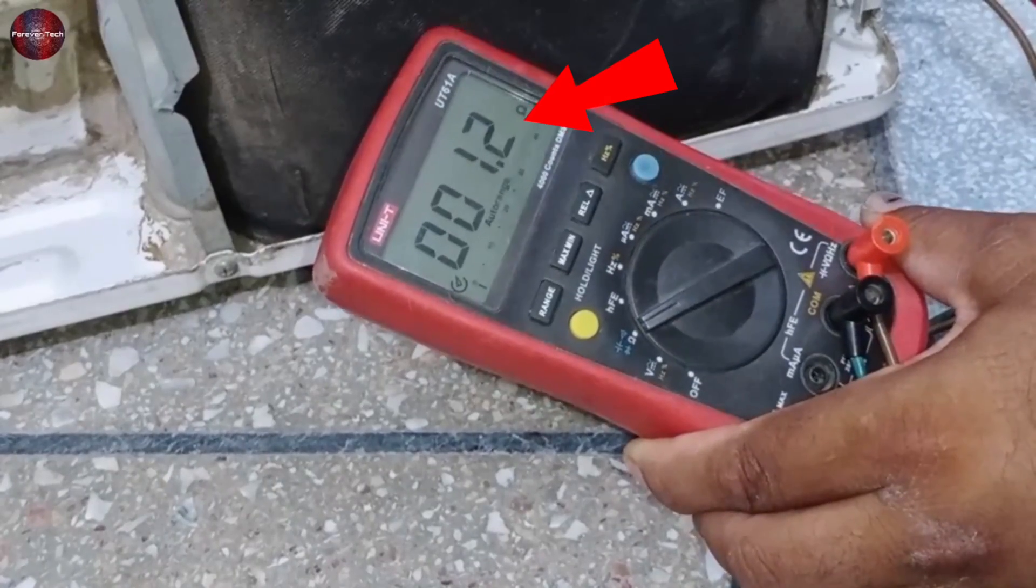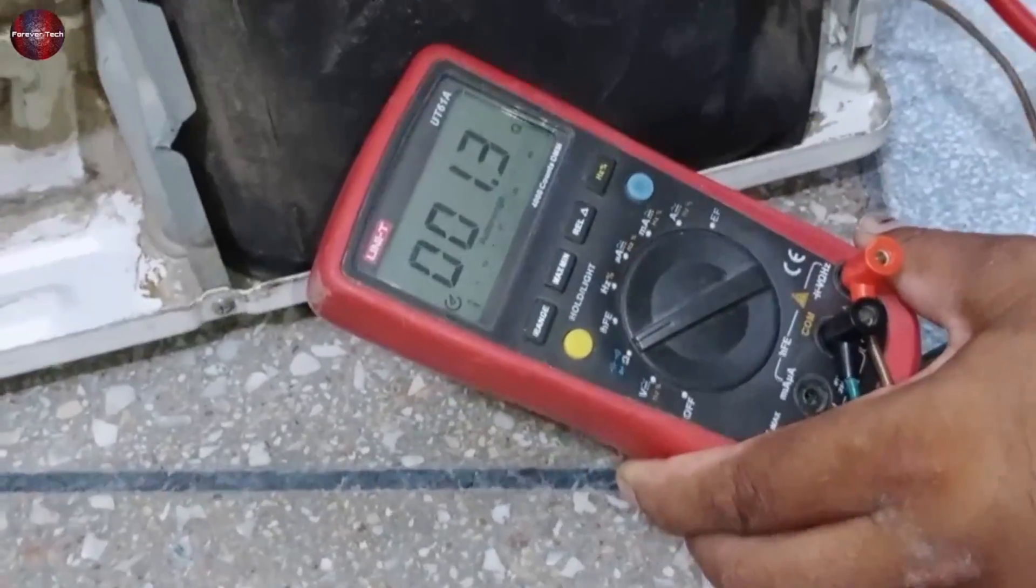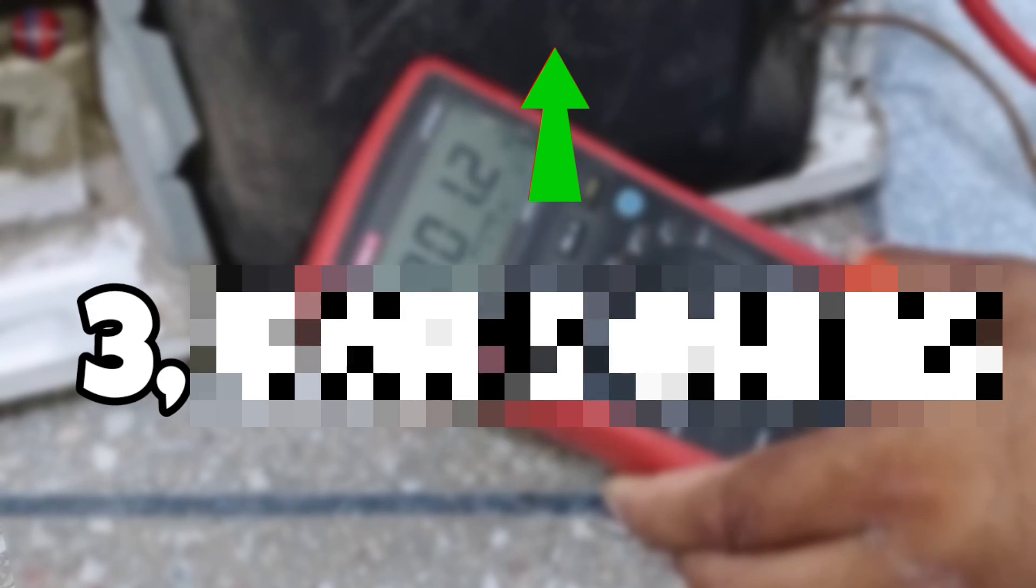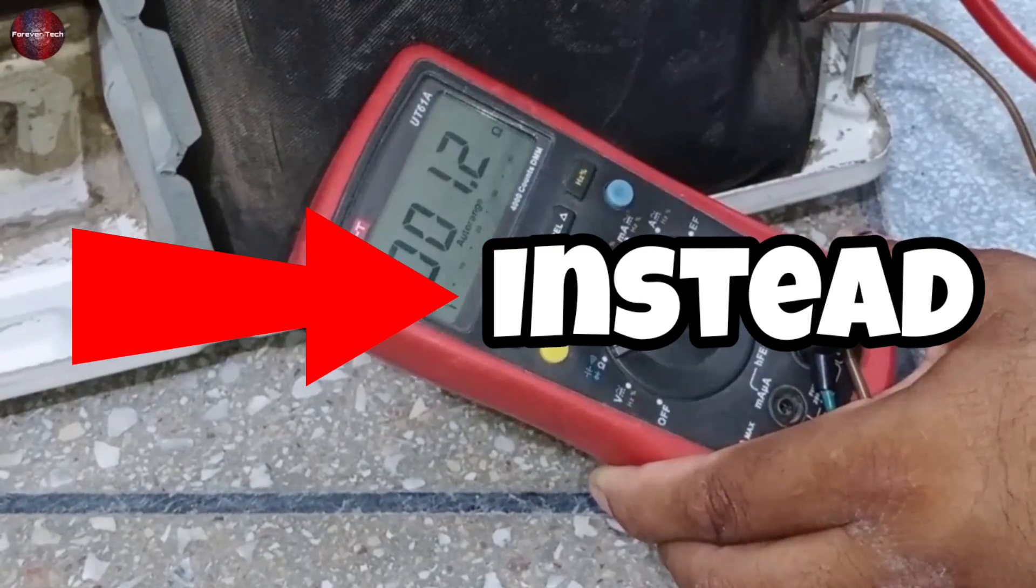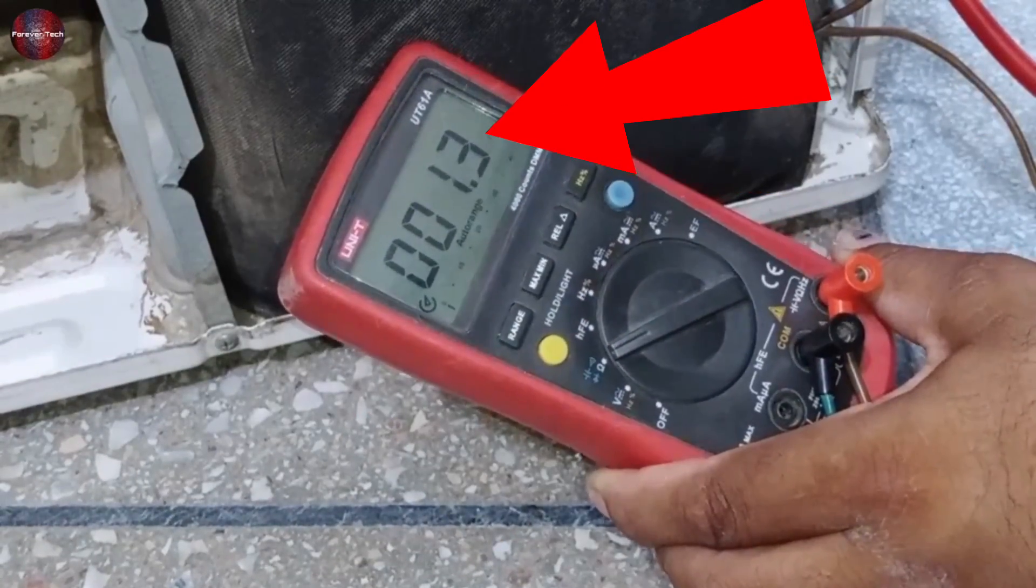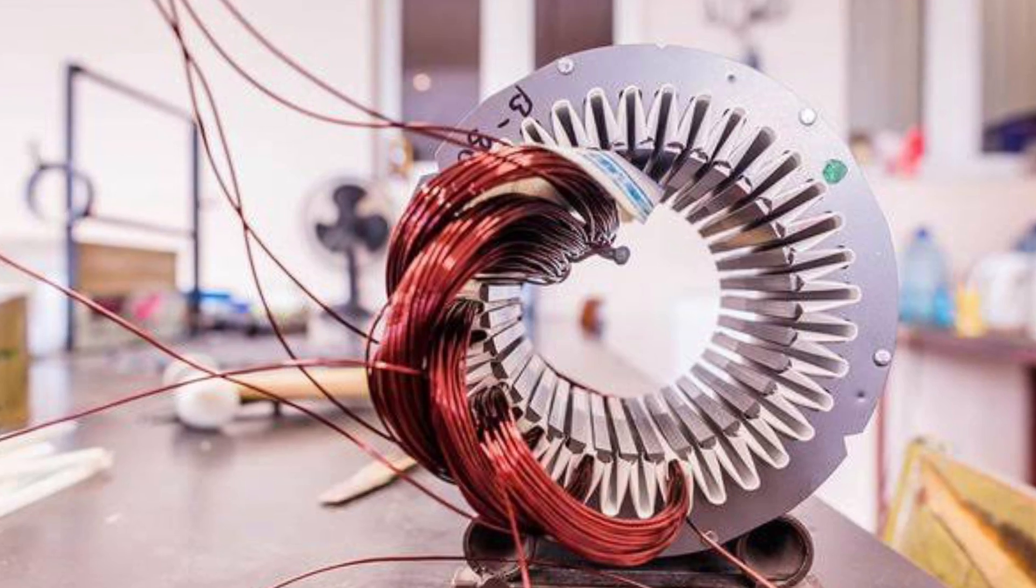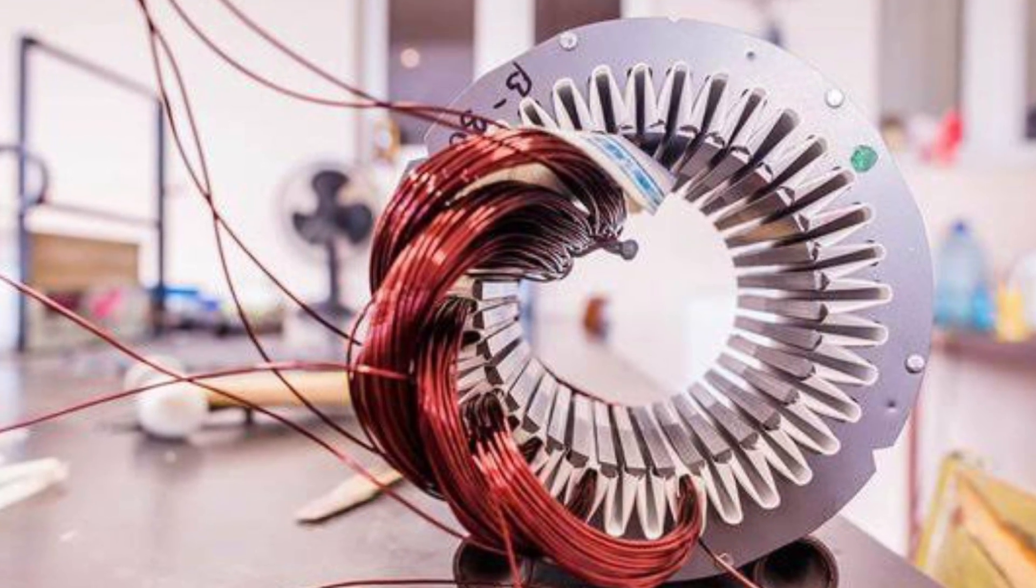All the values of the compressor terminal should be the same. If the reading difference is in points, no problem. The reading should not rise to 3, 4, or 5 ohms. Instead, it should be near the value of 1.2 ohms. Now it means that the value is correct for the compressor and the compressor winding is electrically in good condition.